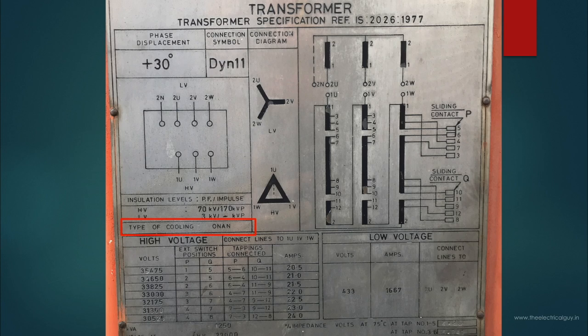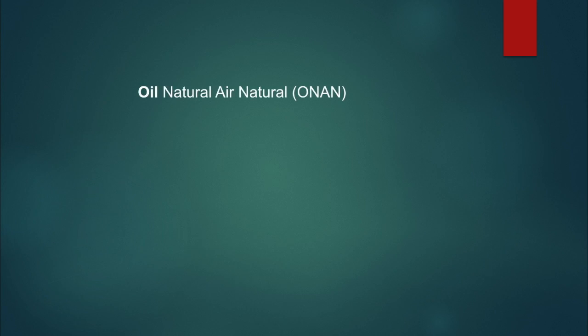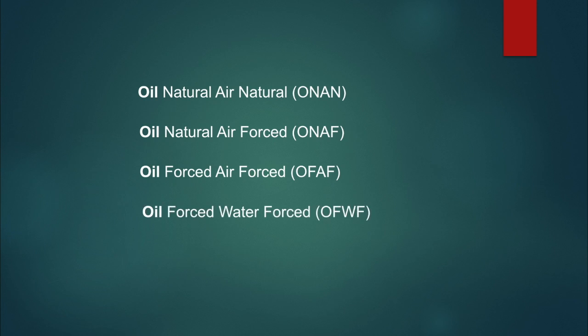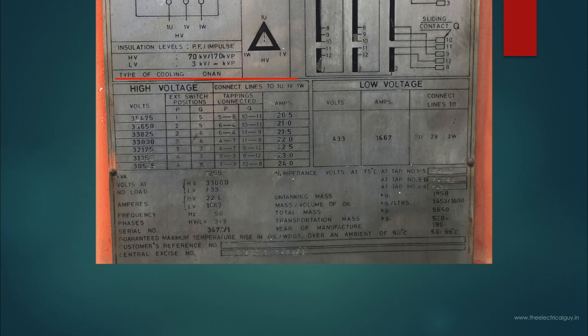Moving on here you can see type of cooling. Here it is mentioned ONAN. This indicates oil natural air natural ONAN. There are some other techniques as well which includes oil natural air forced ONAF, oil forced air forced OFAF and oil forced water forced OFWF. These are some of the techniques used to cool the transformer.